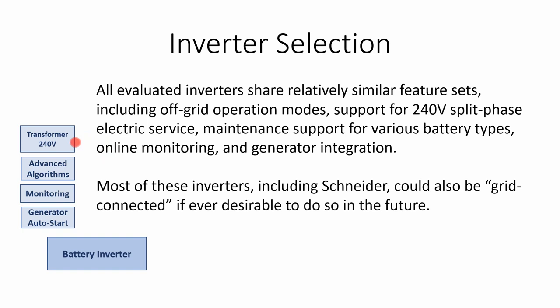off-grid only inverters. And what might be nice about an inverter that is not listed for a grid connection is it might be cheaper than an inverter that has gone through the UL listing process and has all these safety provisions built into its hardware and software to disconnect from the grid during an outage and transfer onto a critical load panel. You could avoid some of that stuff if it's off grid. Likewise, code compliance. There's local AHJ jurisdictions that require external disconnects and external transfer switches, and you might be able to get an off-grid inverter that has all of that stuff built into the inverter cabinet itself. But if you tried to use those components, you wouldn't get through a grid-connected inspection.